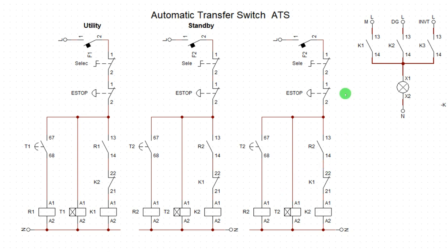It's all right. So what you need to do again now, and it's very important, is to choose which one of these three alternate sources of power I want to make a priority. You are going to decide that with the end user. The end user will have to choose which source of power to prioritize as the prime source, that it must be available and knock off the rest of the sources. Unless that one is not available, that is the only means that any of the other two can come in. So you have to choose.